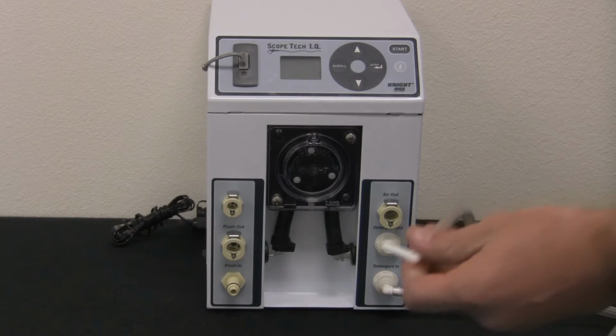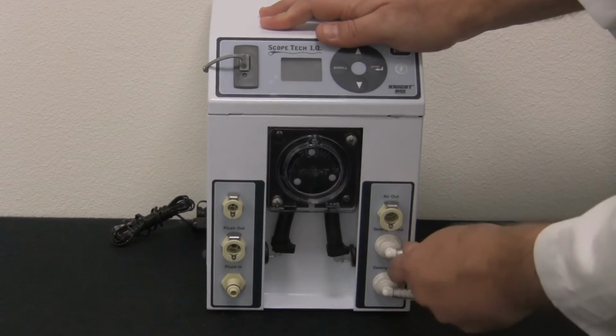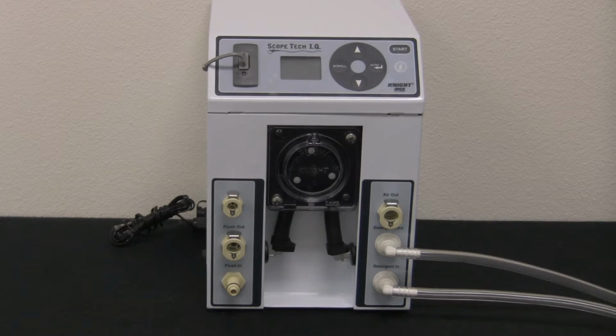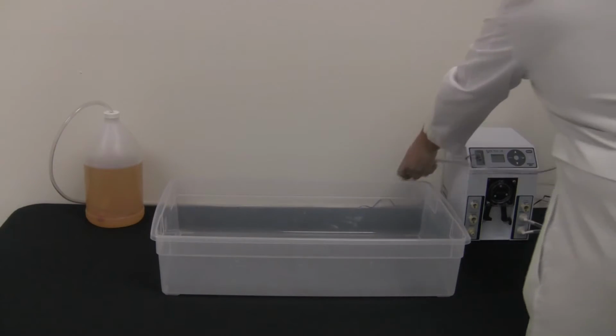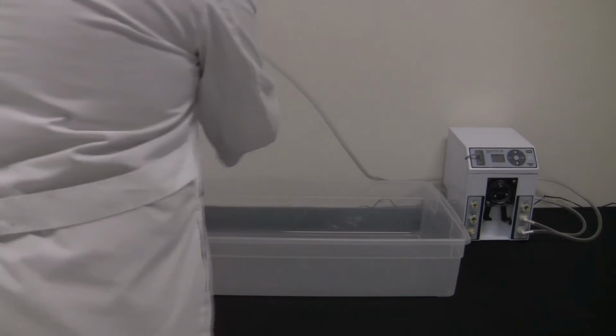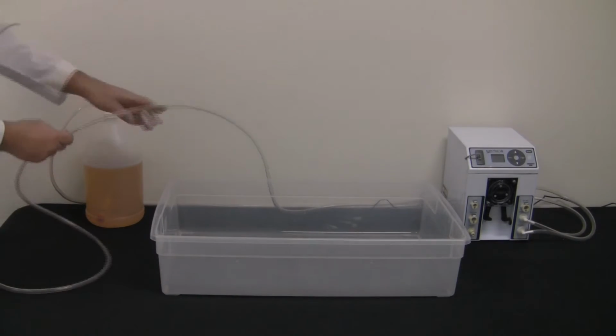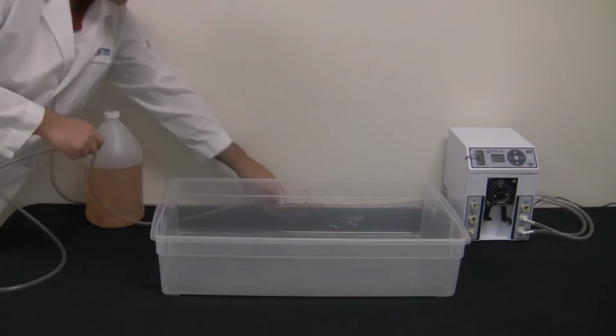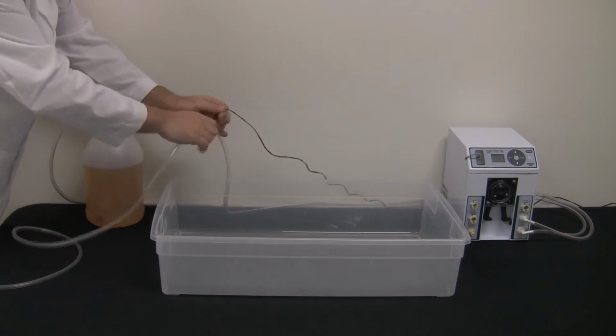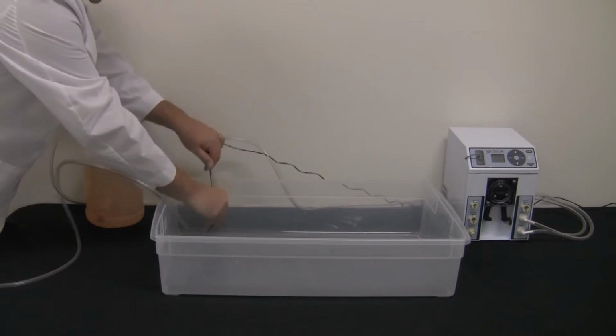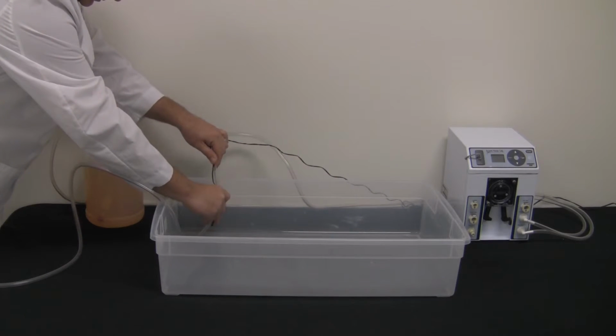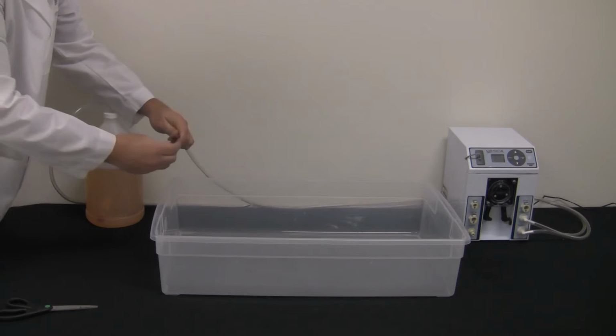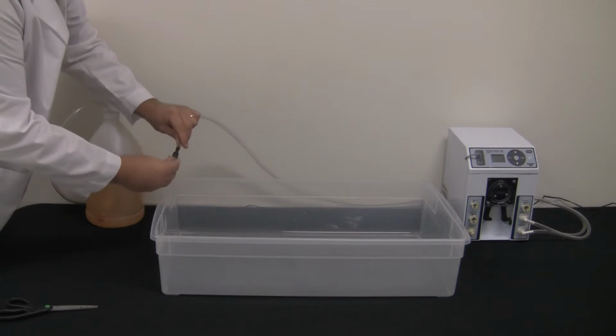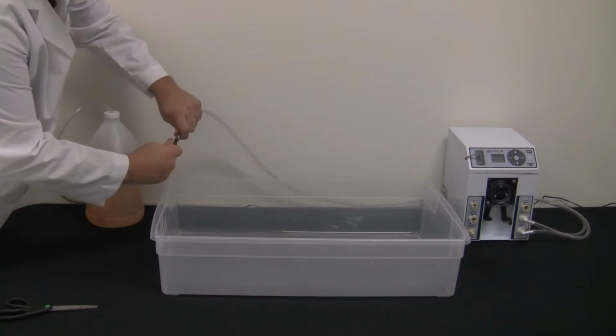Next, connect the detergent discharge tube to the ScopeTech IQ by pushing the detergent discharge tube fitting into the detergent out port on the bottom right of the unit. Route the detergent discharge tube and the temperature probe to the back of the tub or sink where they will be mounted, just above the bottom between 1 and 3 inches, depending on the total volume of the sink fill. If needed, remove the check valve and trim excess tubing, then reinsert the check valve. Make sure that the arrow on the check valve is pointing with the flow of the detergent.